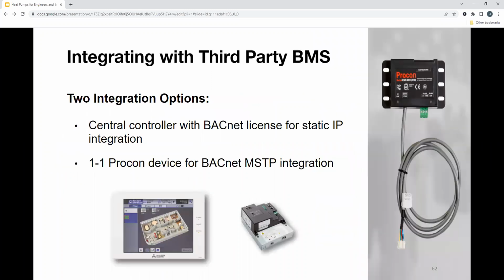So integrating with third-party BMS systems, typically we are integrating with BACnet. That's kind of the most popular. And there are two ways to do that. I just mentioned one, which is using a central controller. You are able to purchase a BACnet license, enter that into the central controller, and then get a static IP address for integration. So that is the primary option. You get tons, actually pretty much numerous, monitor and control points. You can do a lot with that.